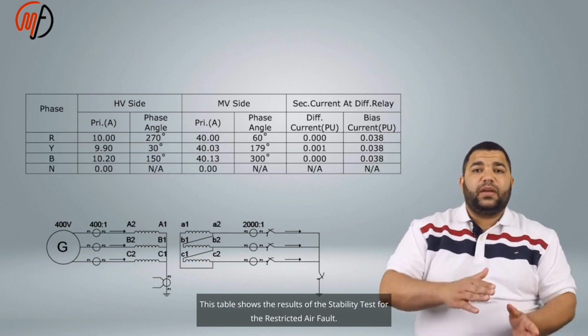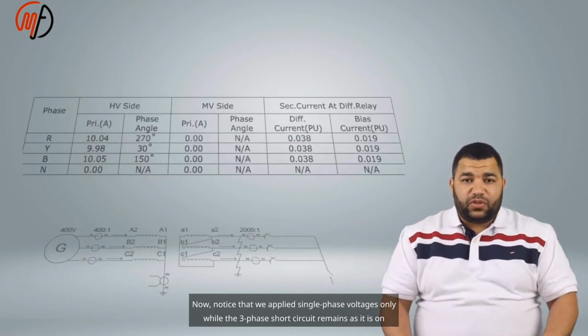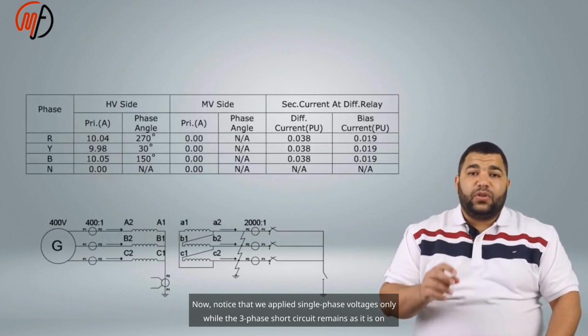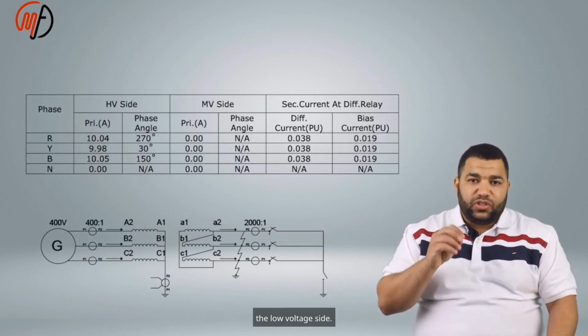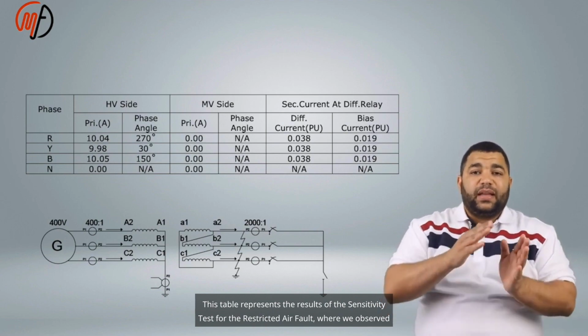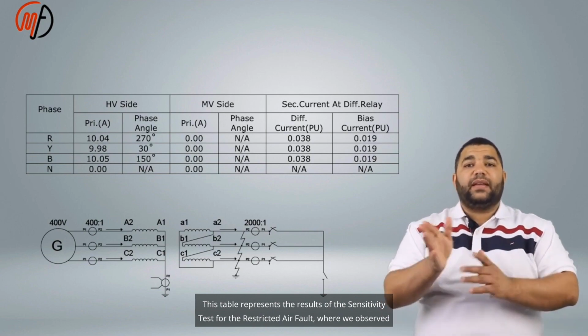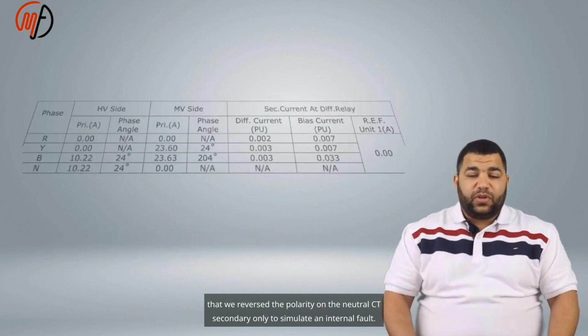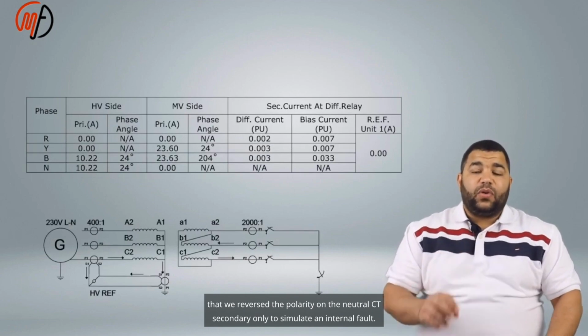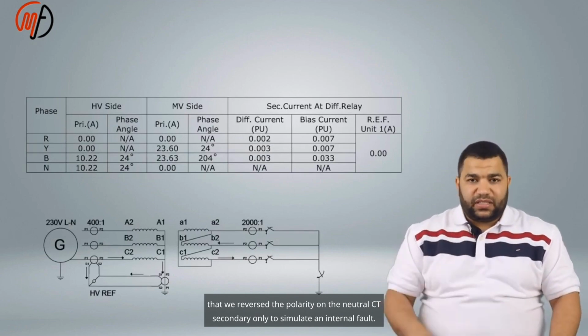This table shows the results of the stability test for the restricted earth fault. Now notice that we applied single-phase voltages only, while the three-phase short circuit remains as it is on the low voltage side. This table represents the results of the sensitivity test for the restricted earth fault, where we observed that we reversed the polarity on the neutral CT secondary only to simulate an internal fault.